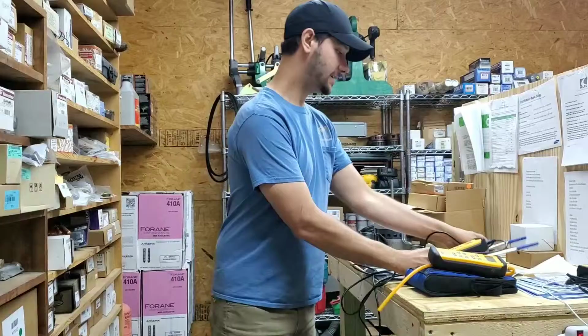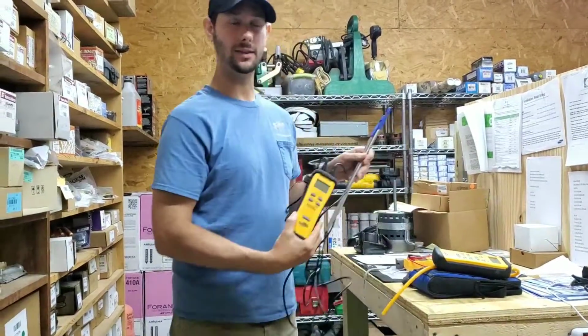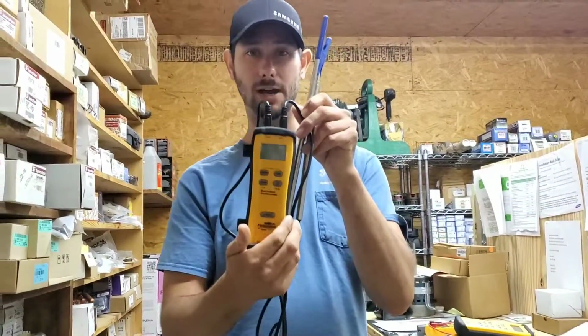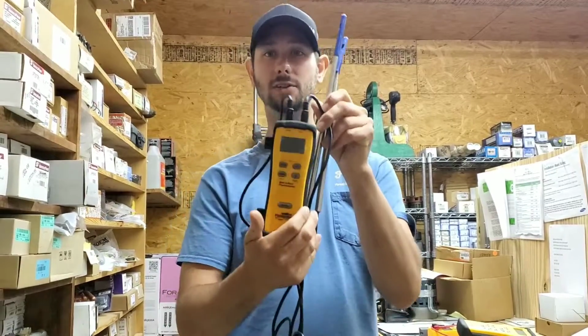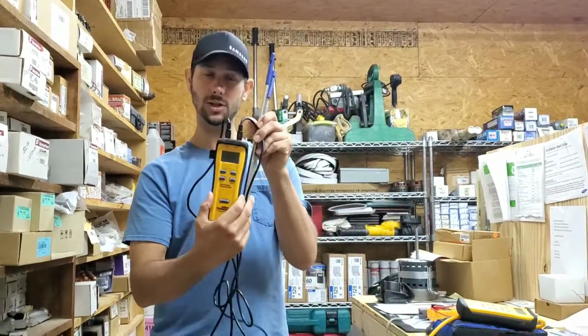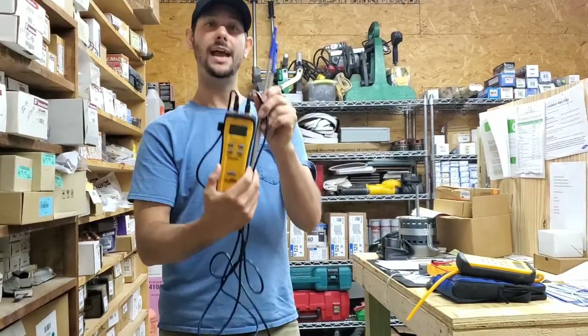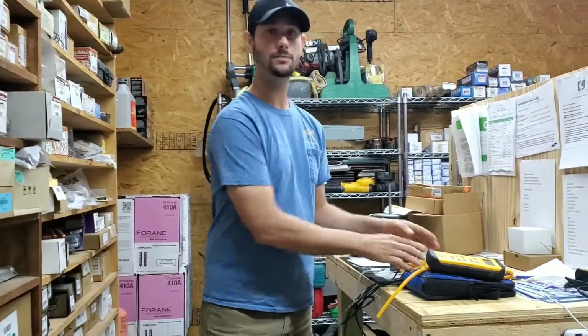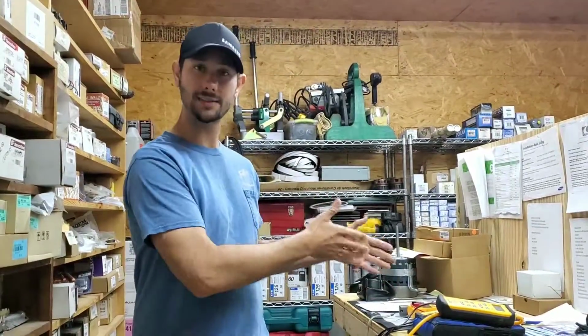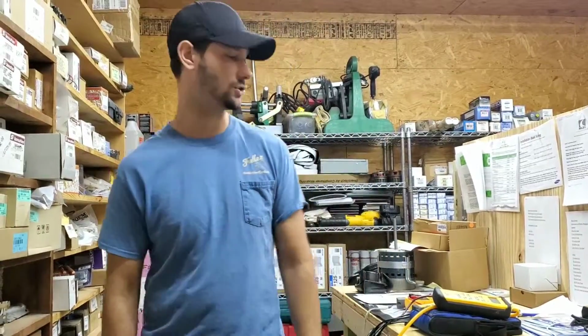The second is a dual in-duct psychrometer. Now this makes the temperature measurement, and you know that we have to measure the supply temperature and the return temperature when you install a new unit, and you have to have a certain temperature split, otherwise you have to make an airflow adjustment. Okay, you have to have that type of tool, and you have to have a temperature split of around 18 to 22 degrees, especially in cooling. In your heating, depending on gas or heat pump, you have a certain temperature split there as well.